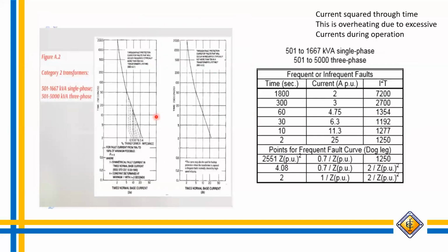So for a category 2 transformer, we have 501 to 1667 kVA single phase and 500 to 5000 kVA three phase. You can use this table in determining the damage curve of your transformer. Here, you just change the impedance. Whatever the impedance of your transformer is, this curve will definitely change. Right? The good thing here is, if you plot this in Excel, whatever the impedance of your transformer, if you have many transformers, you can replace the impedance value and it will generate the damage curve of a particular transformer under category 2.